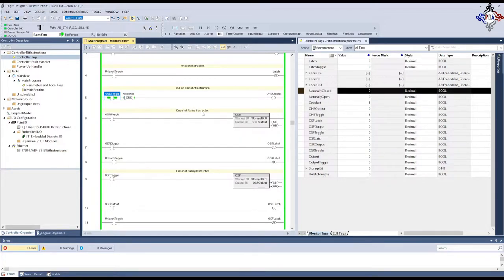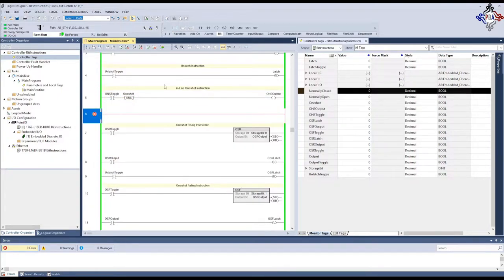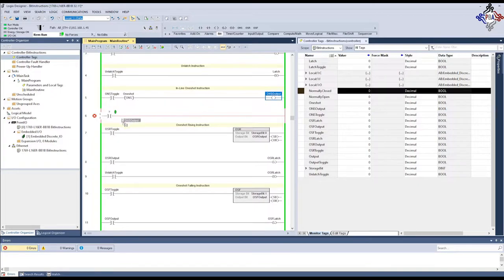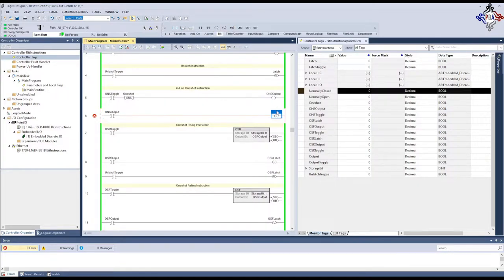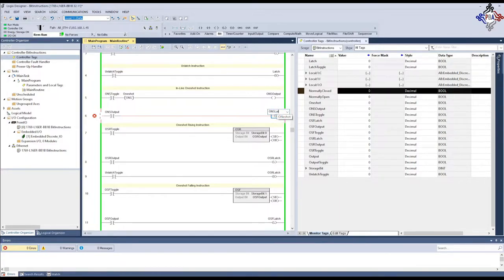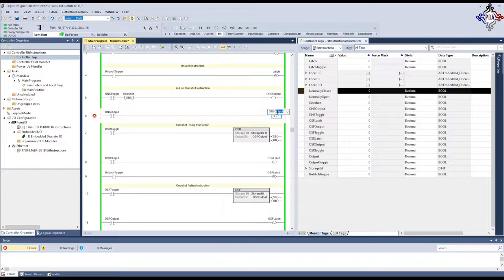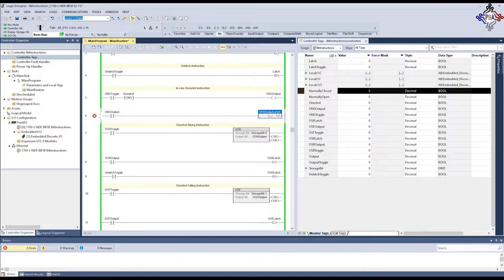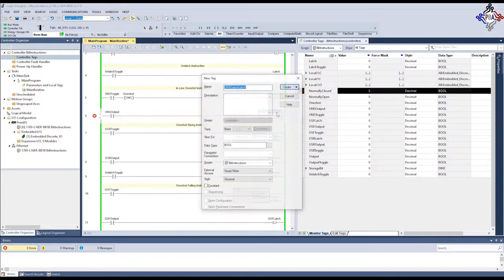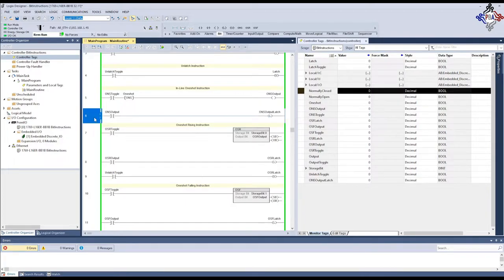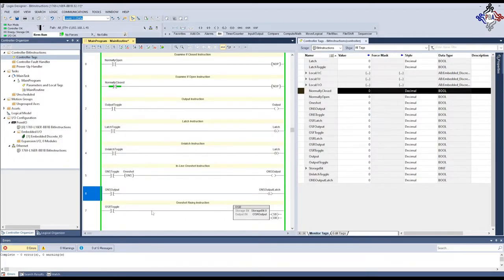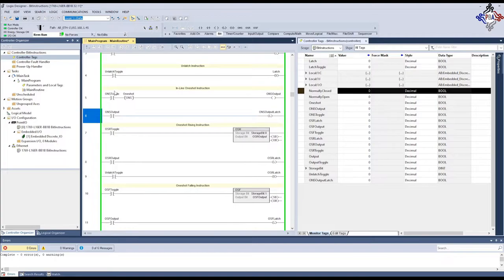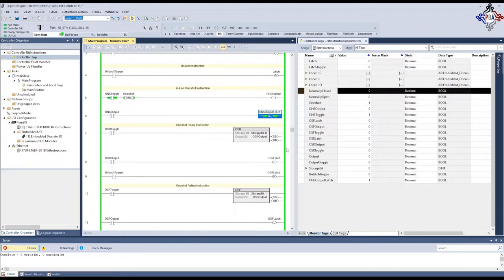I'm going to call this one, let's call it ONS output latch. We're going to create that tag and finalize the edit. Now, when I toggle this on, instantly this latches. But, you'll notice that this output does not latch. It does not stay on. The one-shot only goes true for one scan of the controller. It can latch or unlatch whatever it wants, but then it turns off again after that next scan.